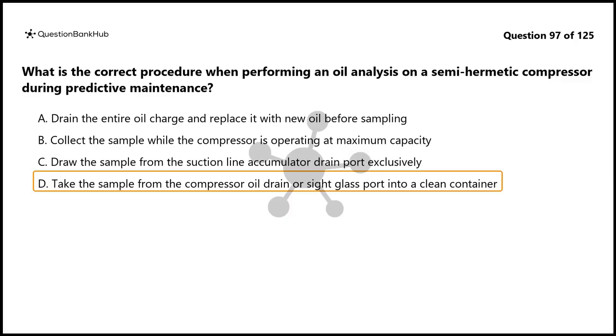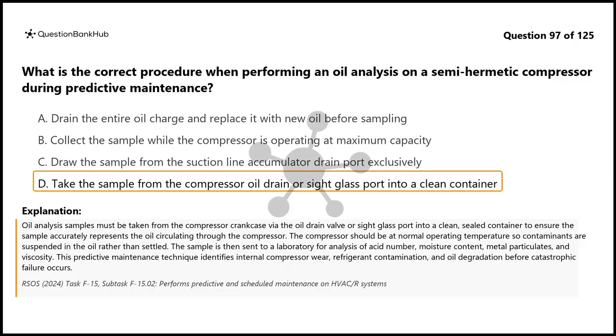The correct answer is D. Oil analysis samples must be taken from the compressor crankcase via the oil drain valve or sight glass port into a clean, sealed container to ensure the sample accurately represents the oil circulating through the compressor. The compressor should be at normal operating temperature so contaminants are suspended in the oil rather than settled. The sample is then sent to a laboratory for analysis of acid number, moisture content, metal particulates, and viscosity. This predictive maintenance technique identifies internal compressor wear, refrigerant contamination, and oil degradation before catastrophic failure occurs.